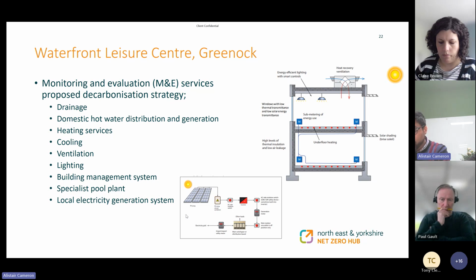So our proposal would be, rather than water to air chillers, we go water to water. And essentially all the rejection from the chiller plant goes to the swimming pool heating system. And that's a very easy win, and provides a decarbonised heat source for the swimming pool, which could significantly reduce the reliance on the gas boilers.